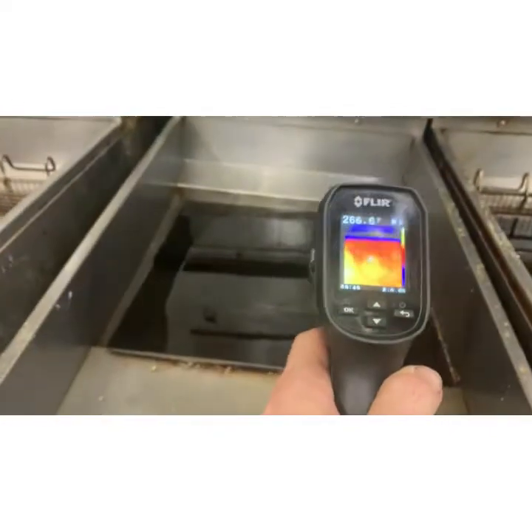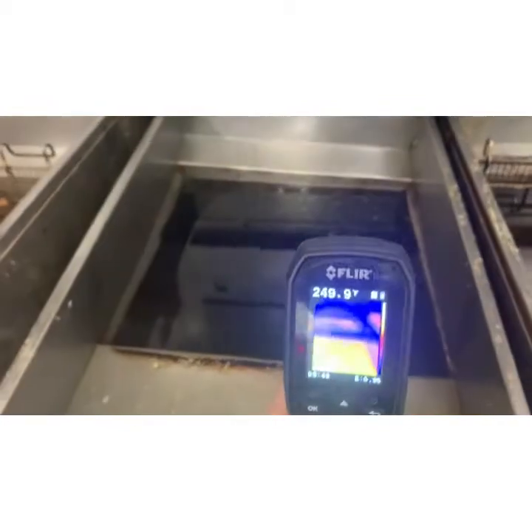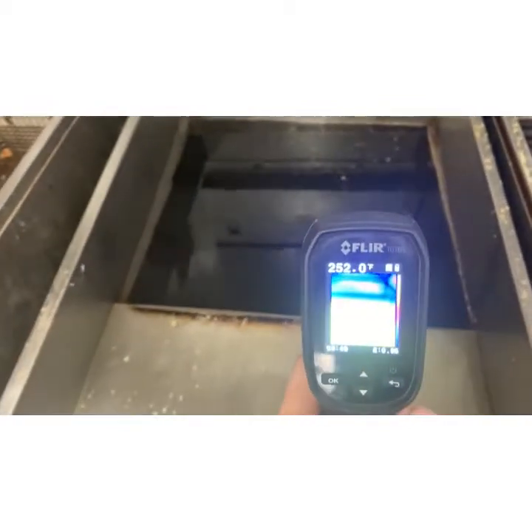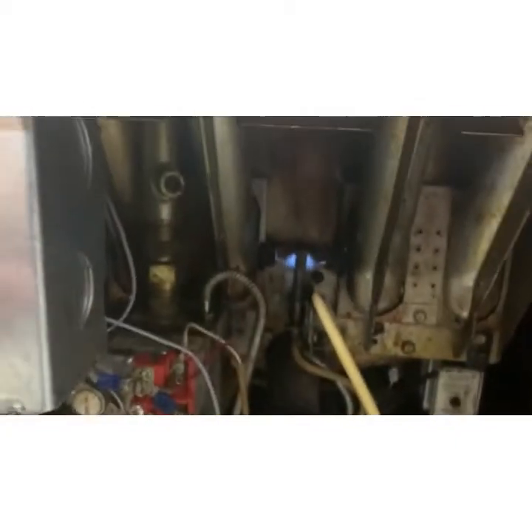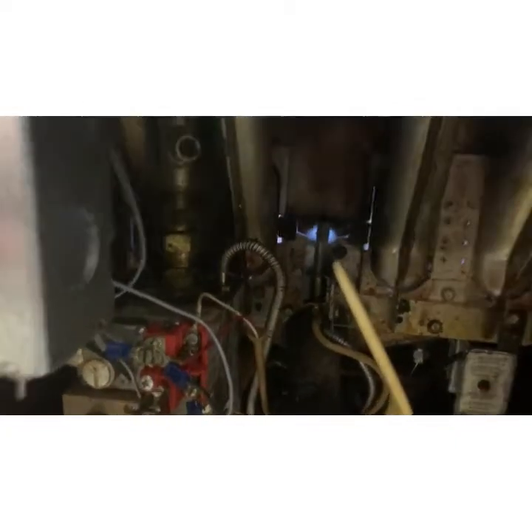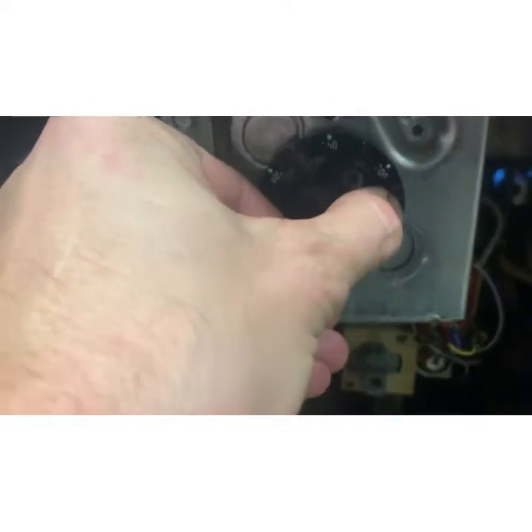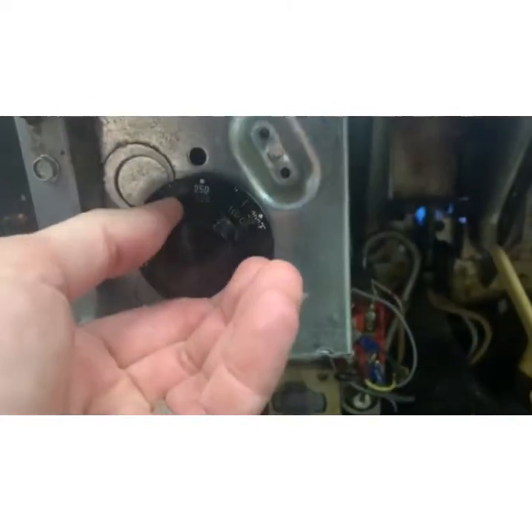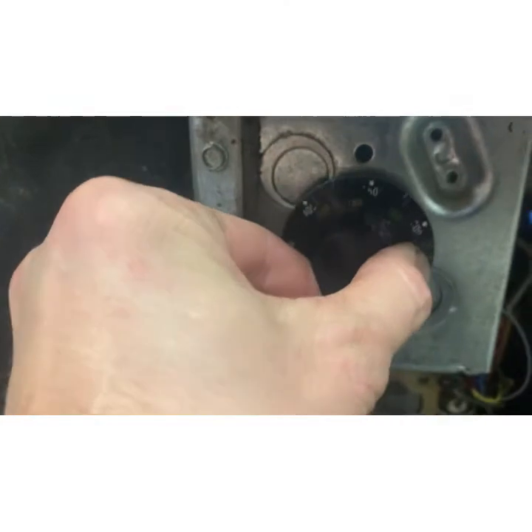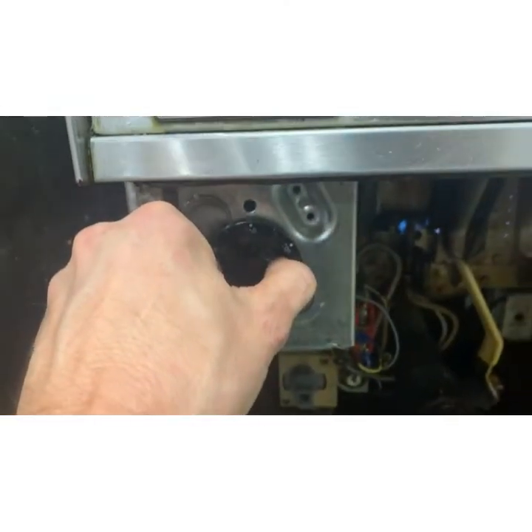Let her go. Okay, so just as a midway testing point, the oil is about 250. When I set it for 250, the burners are off. When I turn it hotter, they come back on. So I'm going to set it for 350 like it's supposed to, and it is now satisfying at the right temp. As long as she shuts off at 350, which I'll verify, that is a wrap.